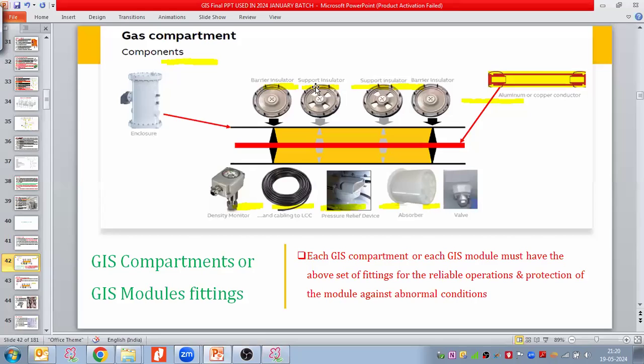Each module must have these fittings. So what are the fittings? Insulators, the barrier insulators and the support insulators, then density monitor, cabling from density monitor to the LCC panels, then pressure relief device, absorber, and gas filling valve. So this needs to be provided in each module.